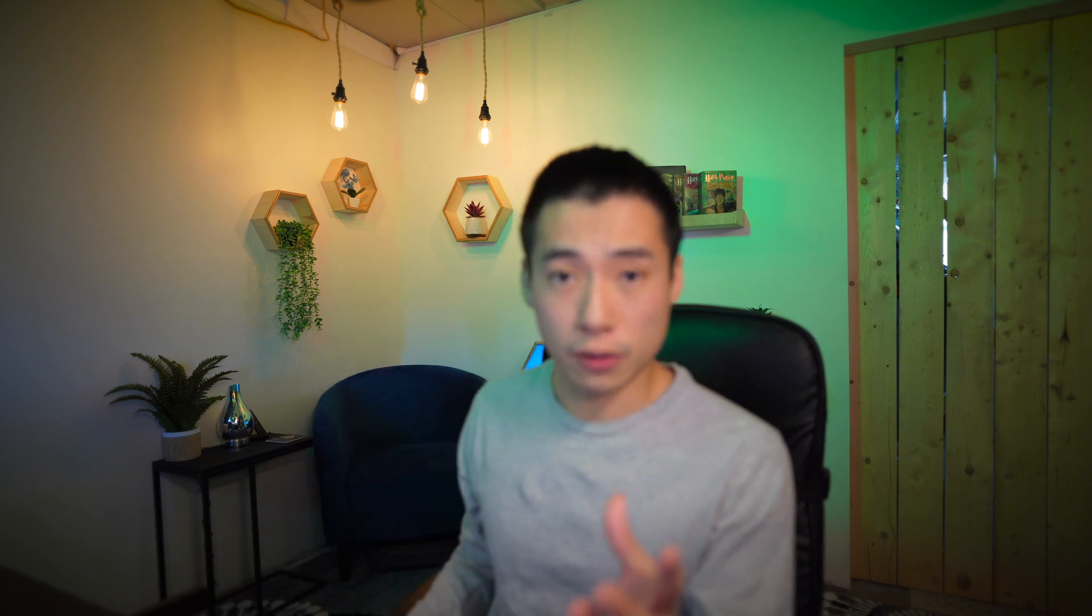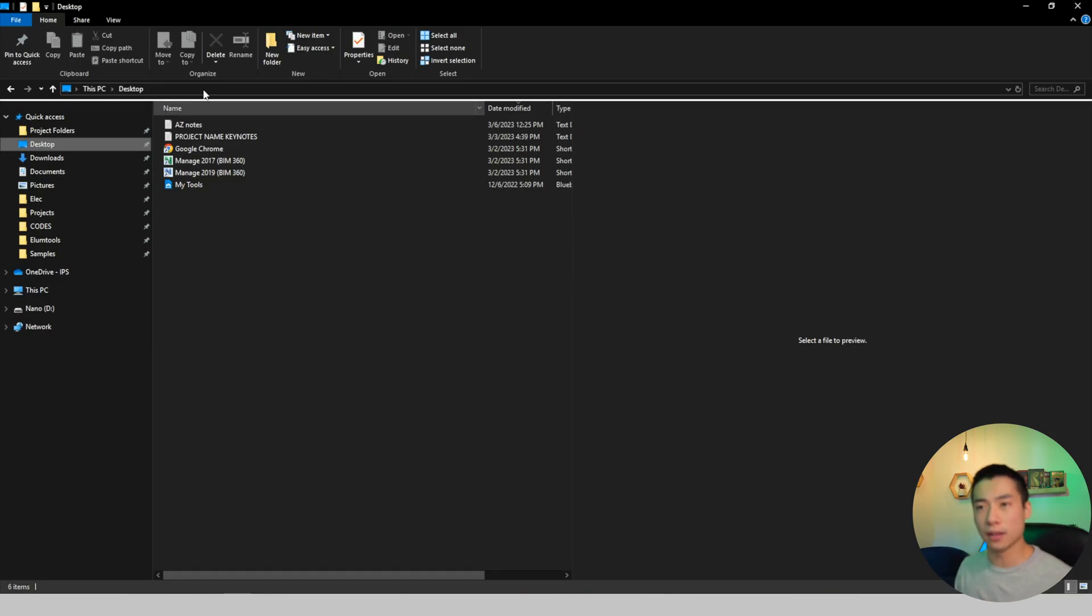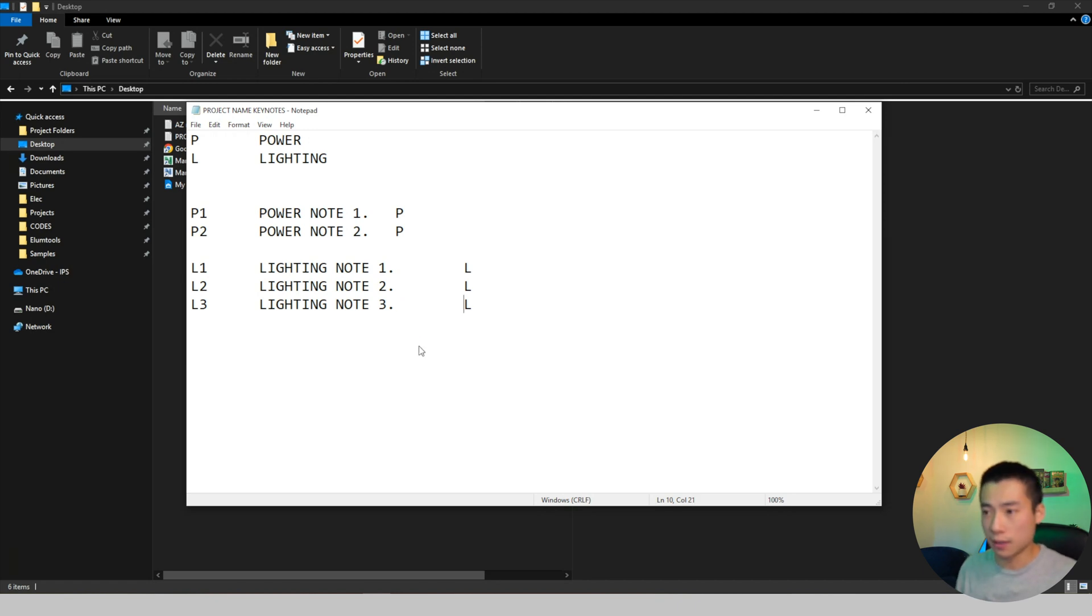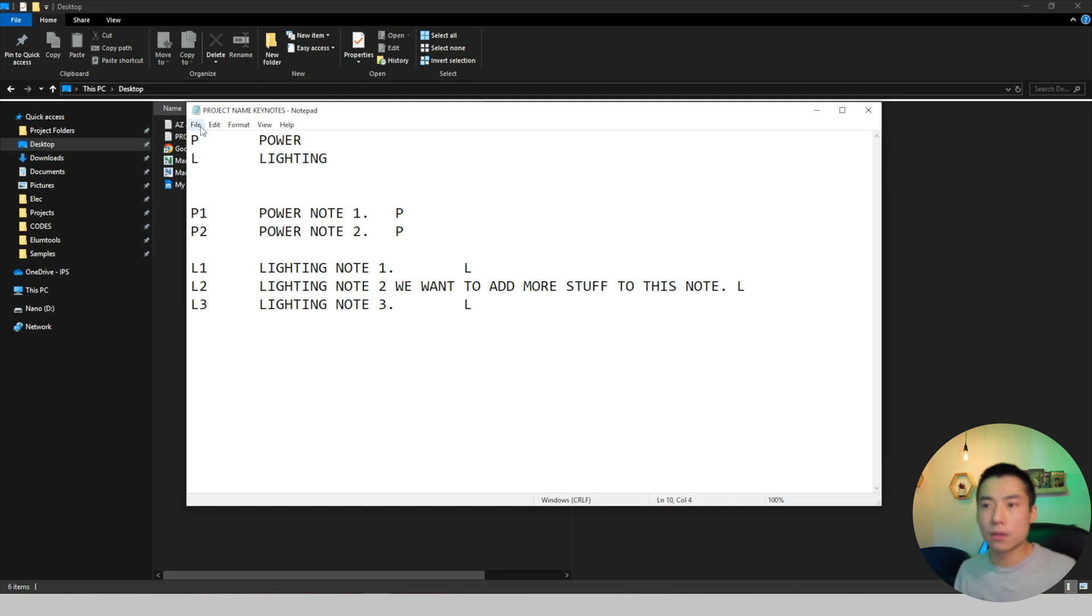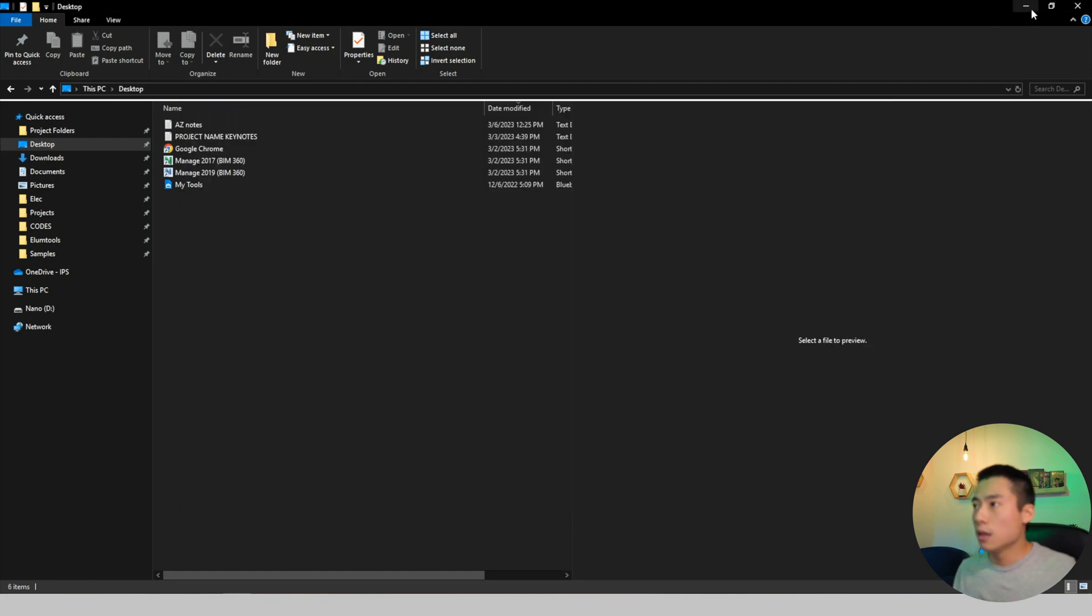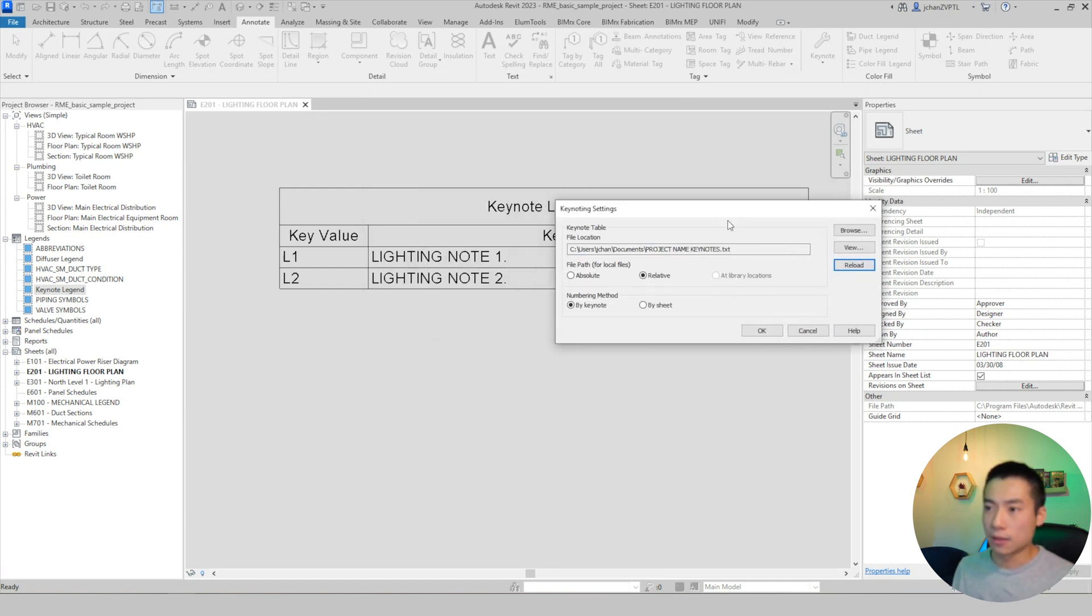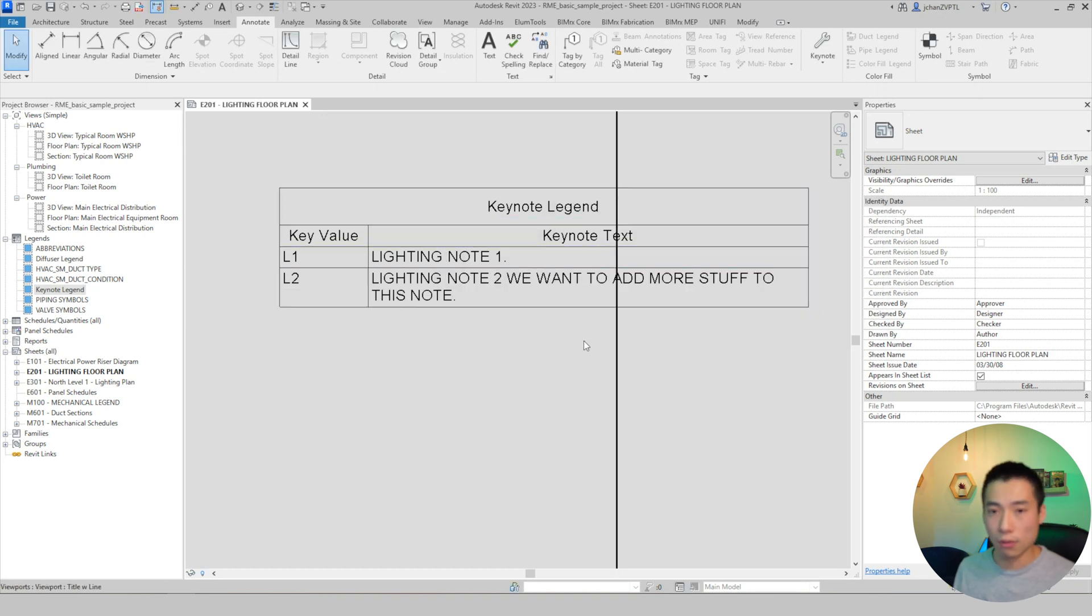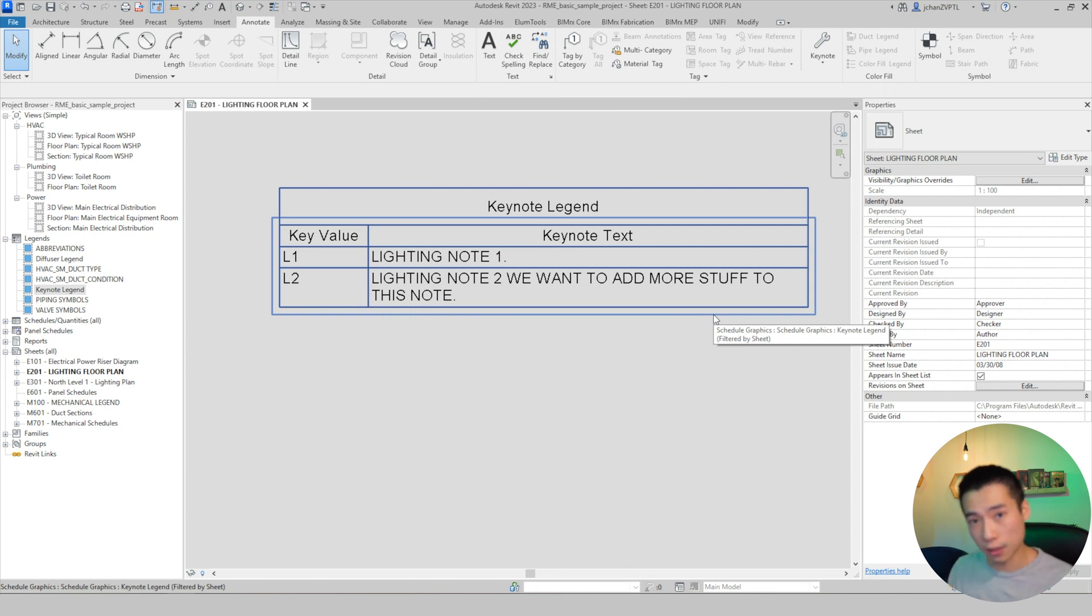So let's say you want to change one of your notes. You have to open up your notepad. So the best way to do that is to go up here under keynote settings again, and then grab this link. So I would copy that and then paste this inside of my windows Explorer to find this file. It'll pop right up. So in here, we're going to fix a couple of things. We're going to delete that space, hit tab. And let's say for note two, we want to add more stuff to this note and we want to save it. So you save the file and then I generally always close it when I'm done. Once you save it, come back to here under keynote settings, you want to make sure you hit reload. When you reload that, the text updates. So you'll see like this says lighting note two. So hit reload and then hit okay. And you can see that the note then populates with the new text. If you don't update, you just hit PDF to send this drawing out. You're never going to have the updated notes. So that's something definitely keep in mind.